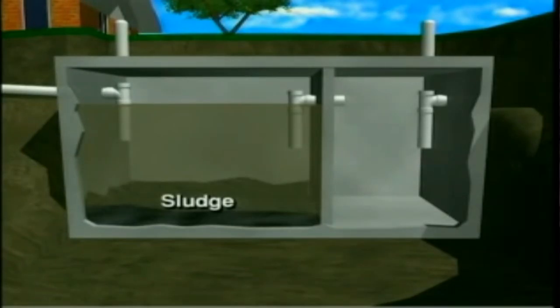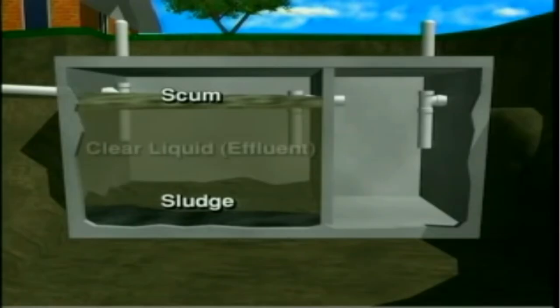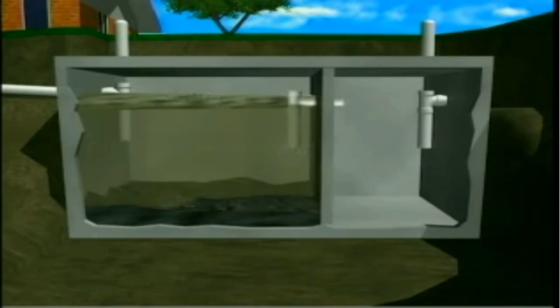Once in the tank, the wastewater separates into three layers. The heavier solid matter, or sludge, sinks to the bottom. The middle layer consists of liquid effluent, while the lighter solids known as scum float to the surface. The sludge at the bottom is partially decomposed by anaerobic bacteria that thrive in these oxygen-free conditions. The liquid effluent then flows from the septic tank into the dosing chamber, aided by gravity.